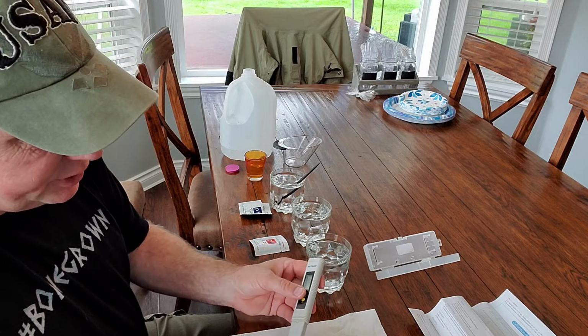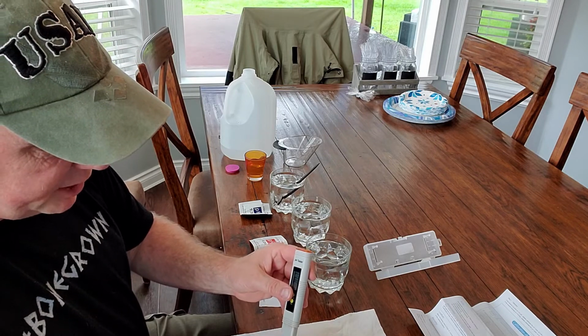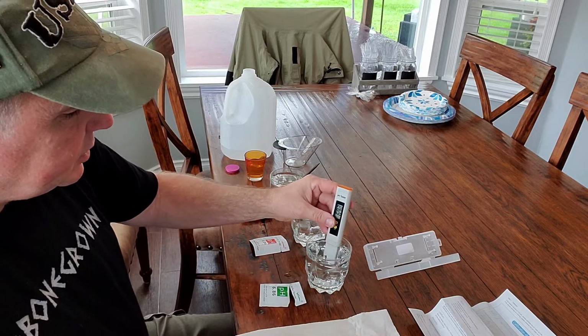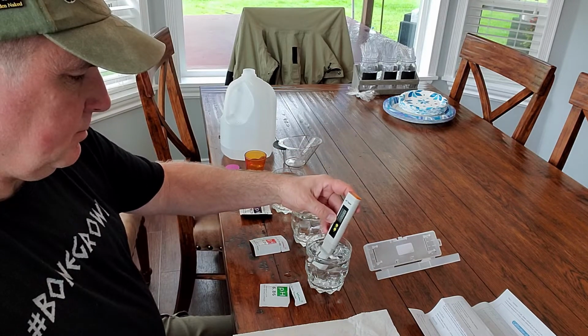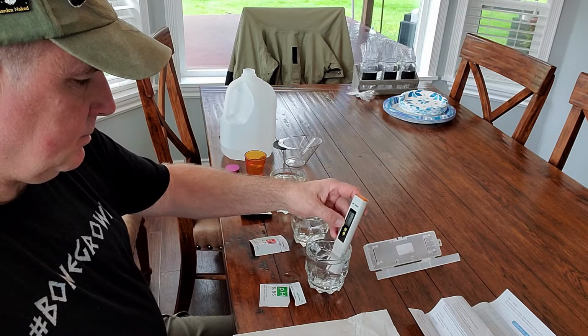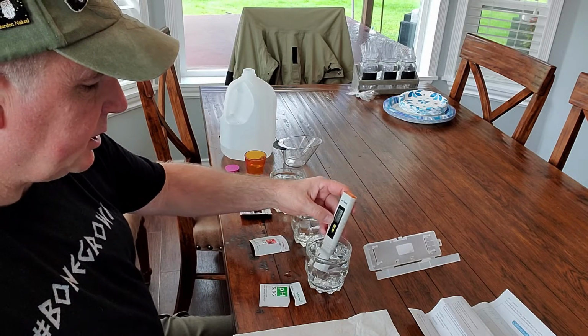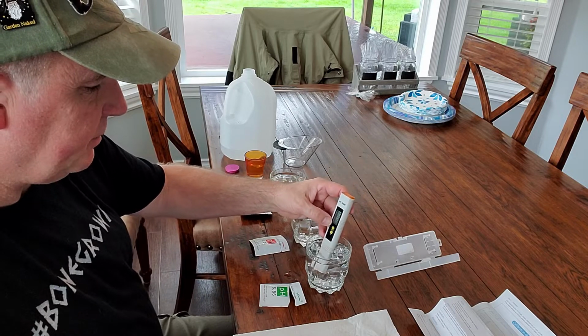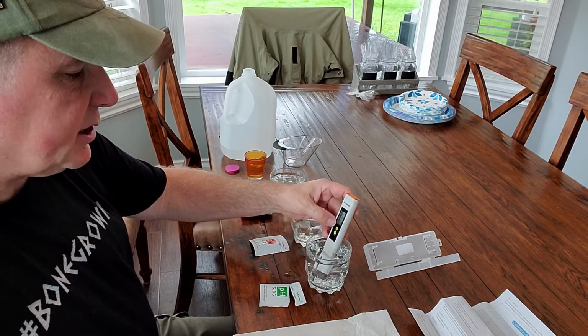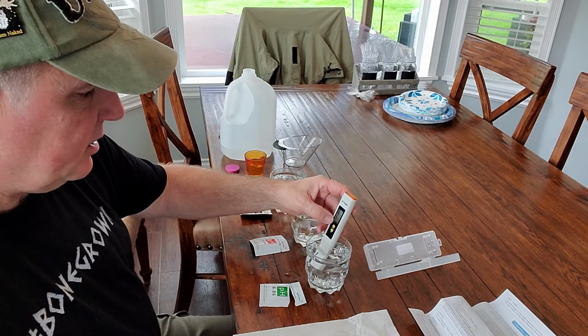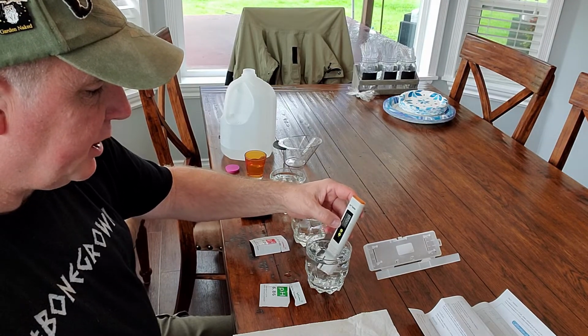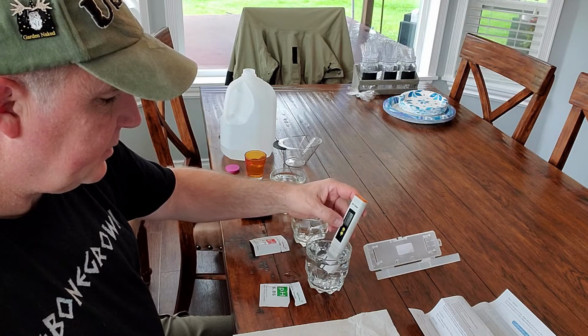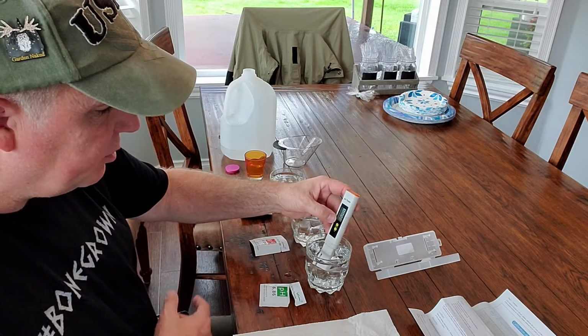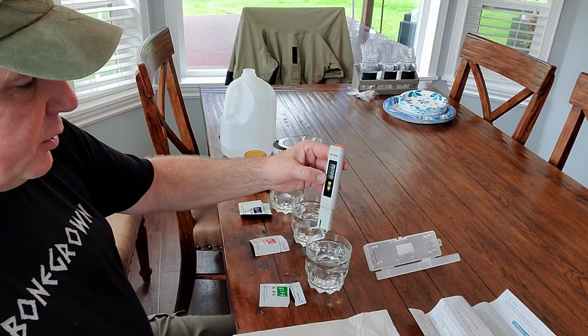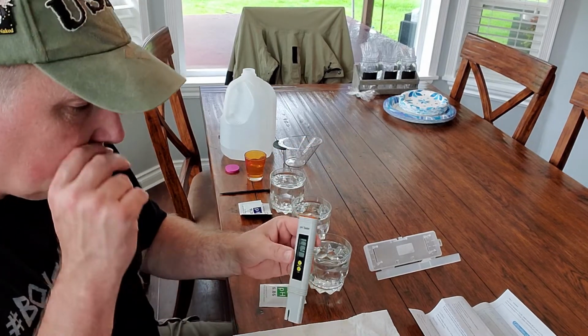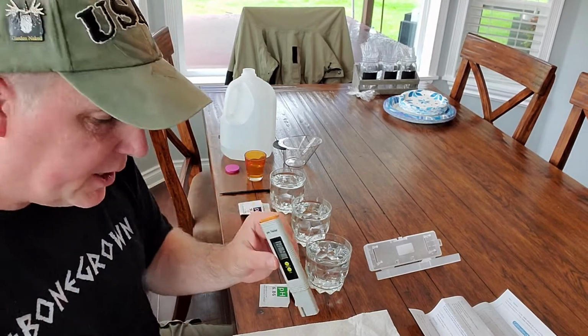Once you get it calibrated, you should be fine to come right into this solution. I want to come in here and see what I get. I'm doing a gentle stirring because I want to make sure the solution is mixing and blending. And right there I'm at 6.85. Let's see if it'll lock in on 6.86. With this particular one, you don't want to go above the water line. And there you go, folks. I was at 6.86. So now I know my meter's dialed back in again.